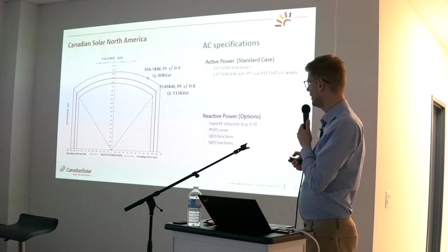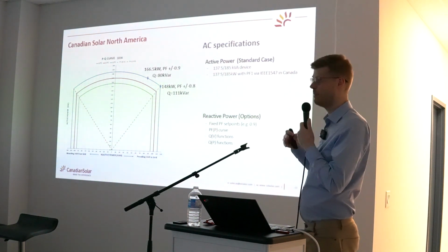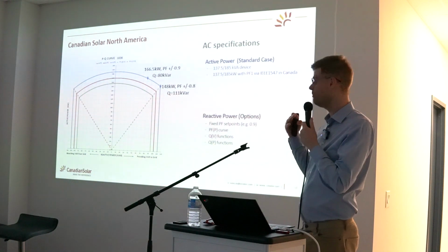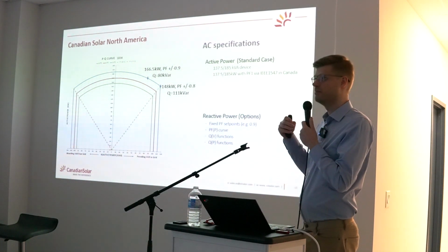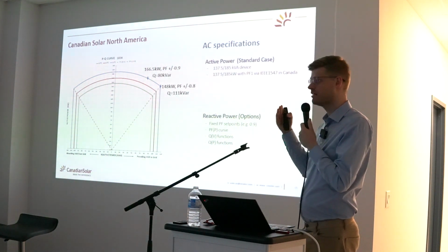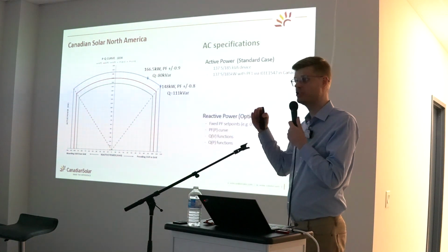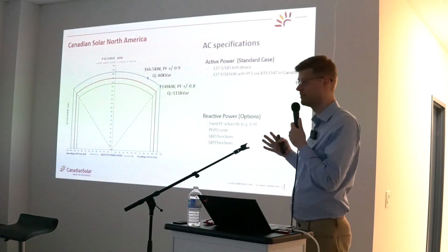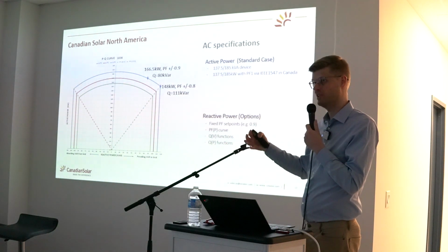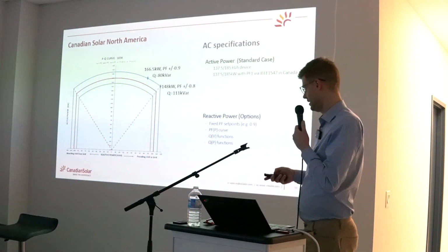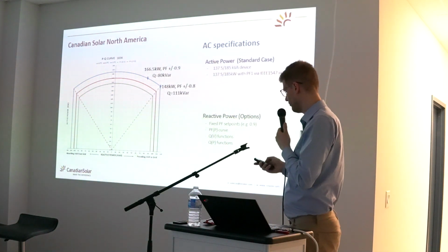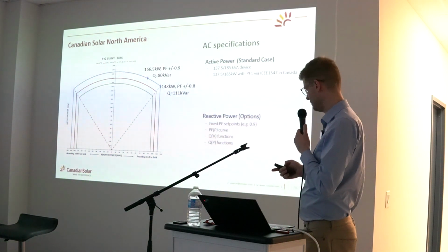Then there are two other models: a reactive power based on voltage and a reactive power based on power as well, where your reactive power component depends on the voltage level of the grid. And that's one of the smart features, that the inverter is helping the grid to maintain voltage level in that Q of V function, for example, or even on the Q of P.